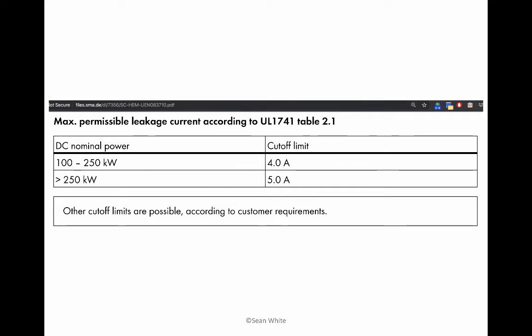Most people who did residential solar 10 years ago had 1 amp fuses in their inverters. And once in a while, if you have enough current, you can have a fuse that's upsized so much that it can't even catch the ground fault. It's like the boy who cried wolf. There were leakage currents, and what leakage currents are is some current that would follow the ground way down, going through the glass of the module. If you have enough modules, there's enough leakage current leaking through that glass that would get all the way through. We don't have to worry about that too much anymore, except when we're doing O&M these days, or on some of the bigger PV systems. So if you're going to do some O&M or work on some bigger PV systems, you might want to be a little bit more aware of this.